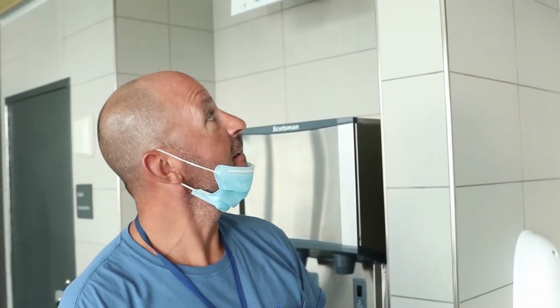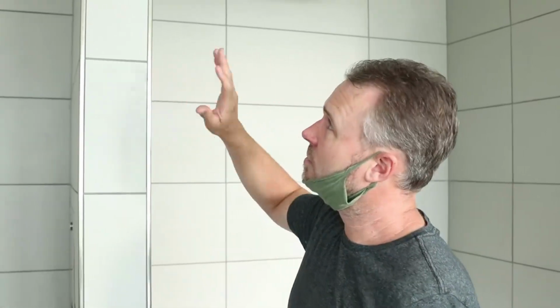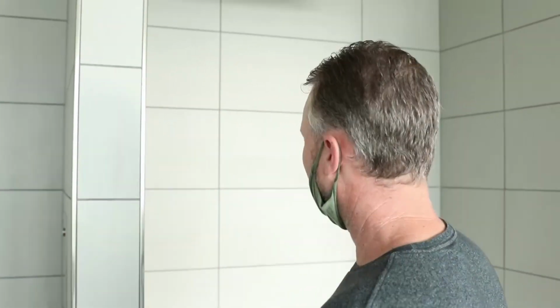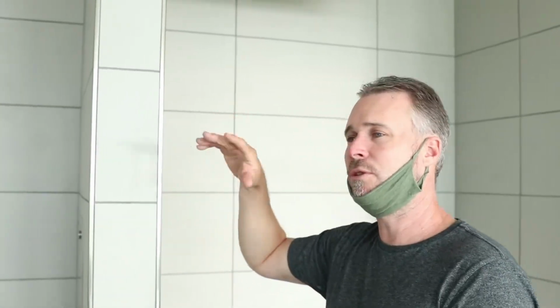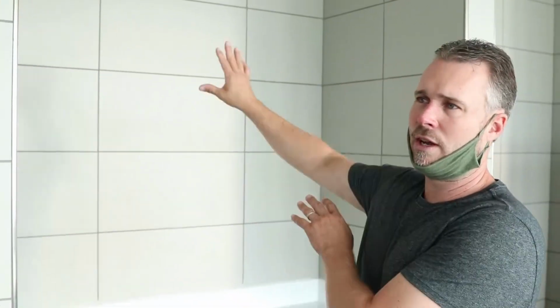And if there's a problem with the damper, you talk to Raph, because he looked at them - I can see his name on there. So this is air handler 2, this is shaft 3. All the fire smoke dampers that come out of this shaft are around this entire shaft. AHU2 serves from the first floor all the way through the 5th floor. The reason being is there's no unit that's serving below where we're standing, so this goes all the way down to 1. AHU2 serves all of the administrative areas across behind the elevators and all of these dining areas.